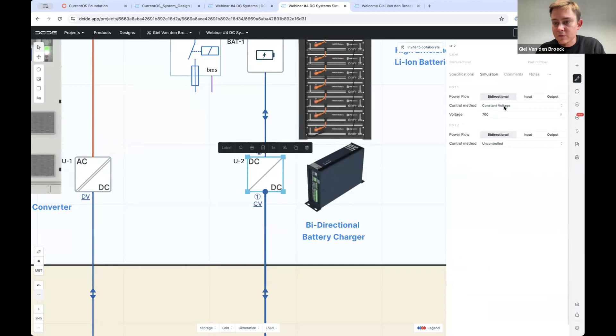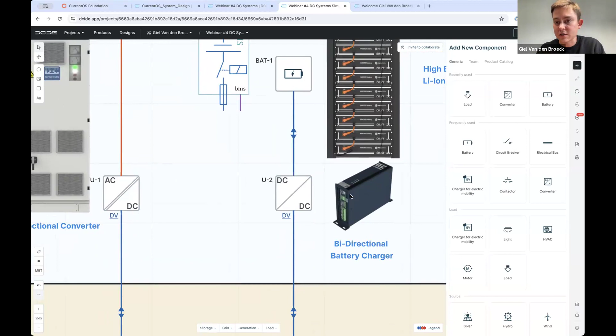So if I go into Droop control mode for both assets, you notice that I can set a Droop resistance, which is the Droop configuration parameter, and a nominal DC voltage of 700 volt. I'm gonna set exactly the same voltage Droop settings on my DC converter. So 100 milliohm, 700 volt DC. Recall that this converter was delivering all the power, and this one was not handling any power. Let's now see how the situation changed.